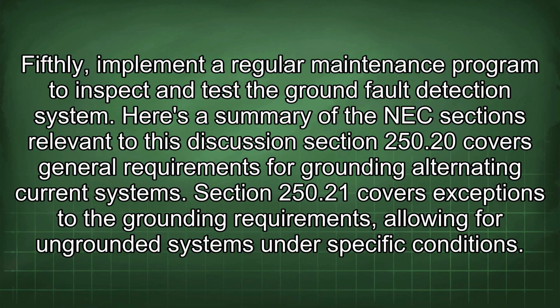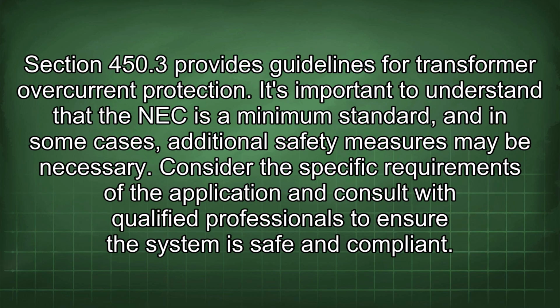Here's a summary of the NEC sections relevant to this discussion. Section 250.20 covers general requirements for grounding alternating current systems. Section 250.21 covers exceptions to the grounding requirements, allowing for ungrounded systems under specific conditions. Section 450.3 provides guidelines for transformer overcurrent protection.